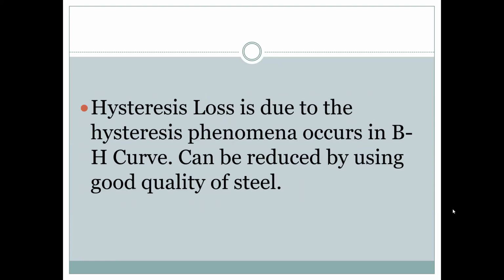Hysteresis loss is due to the hysteresis phenomenon of the BH curve, as I told, and can be reduced by good quality steel. So the BH curve should be as close to ideal as possible. Every time electromagnetic induction takes place, the ideal BH curve has to form. So it will form the B and H loop. It will always be like this; the ideal BH curve should be followed.